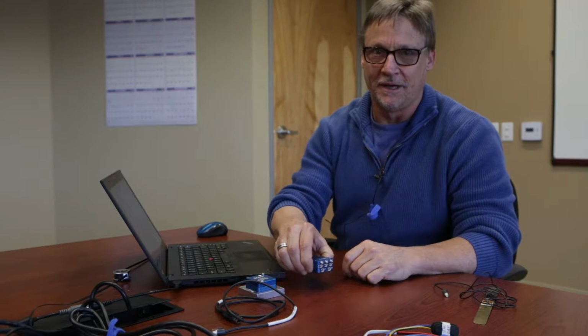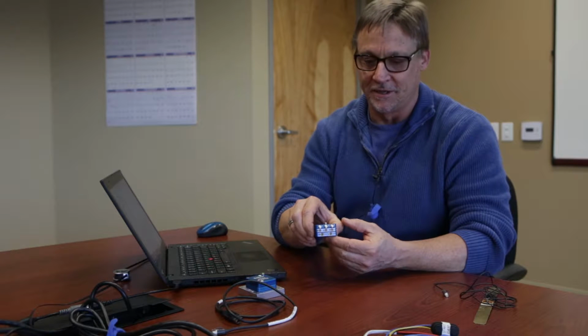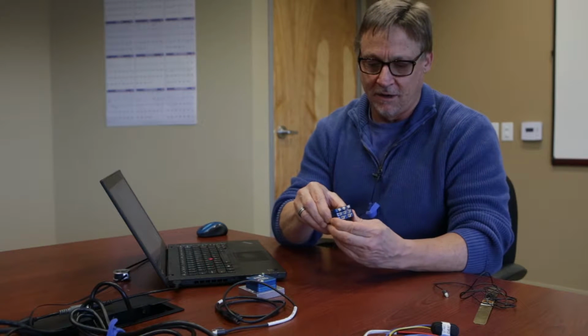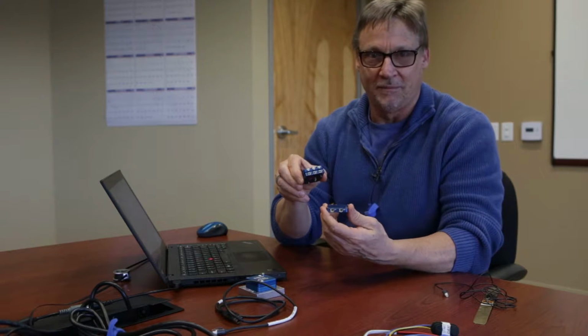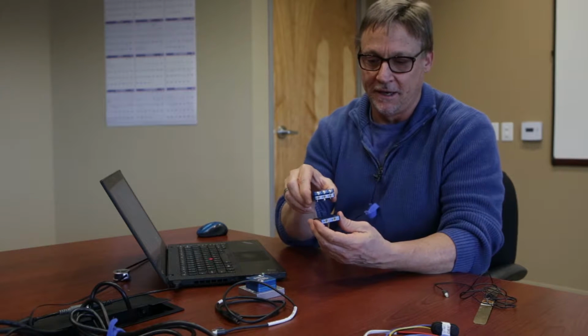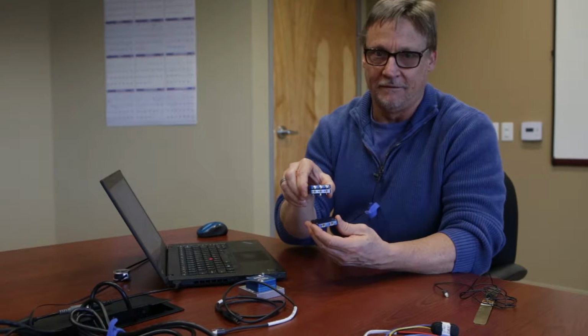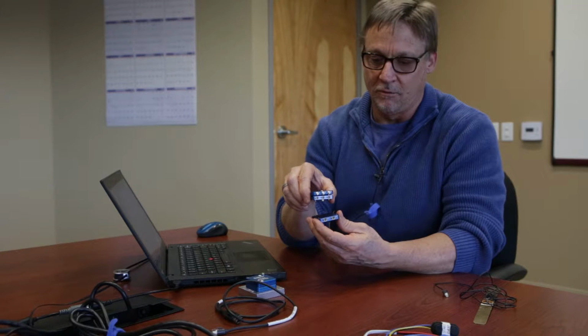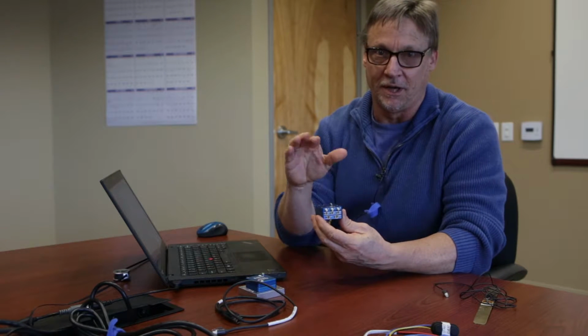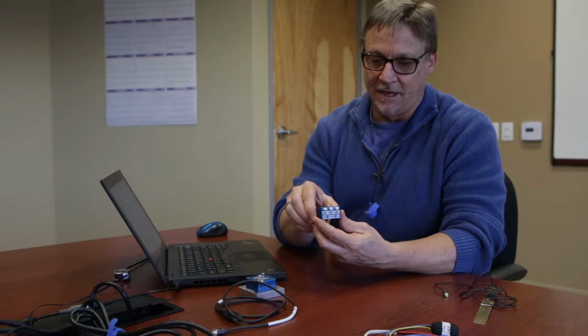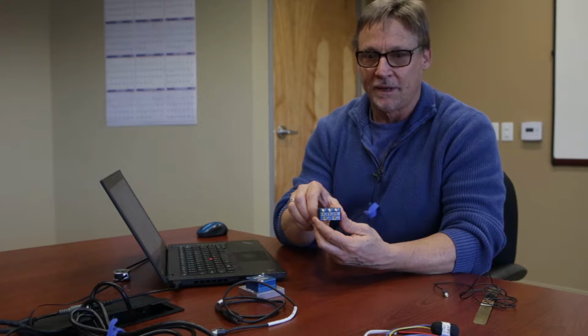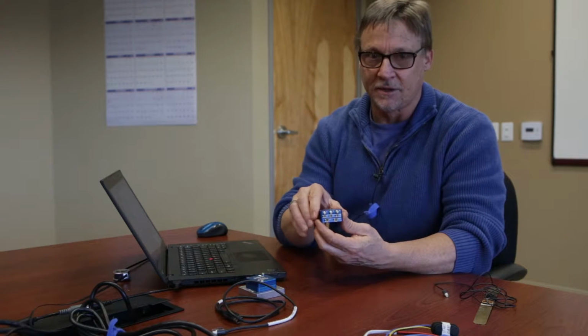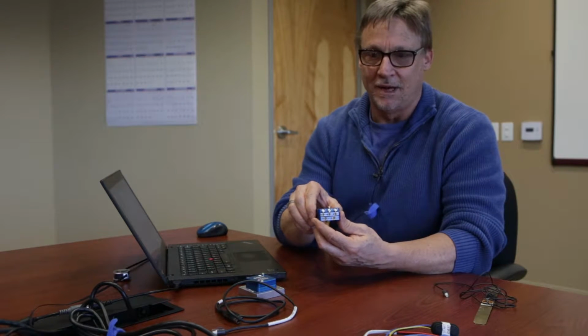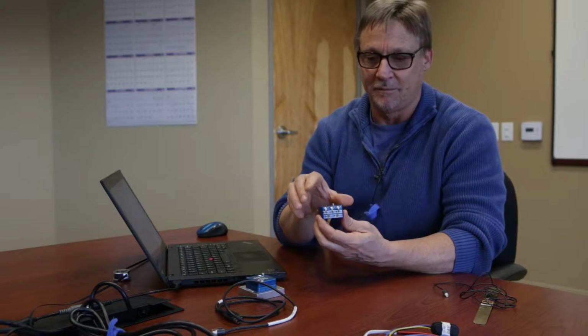The Slice Micro is a highly modular, very portable data acquisition system that is comprised of a base layer, which is fundamental to all configurations, and then a series of transducer layers that we put on top of the base layer to build up a system. Each layer has 3 channels, and we can put up to 8 layers on top of a base, so a maximum of 24 channels per stack.